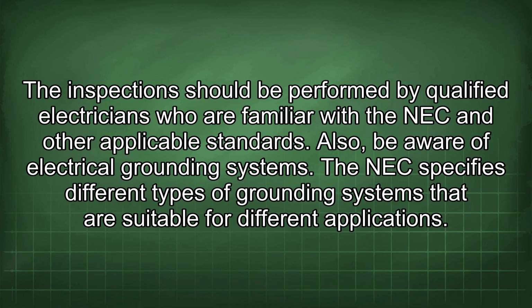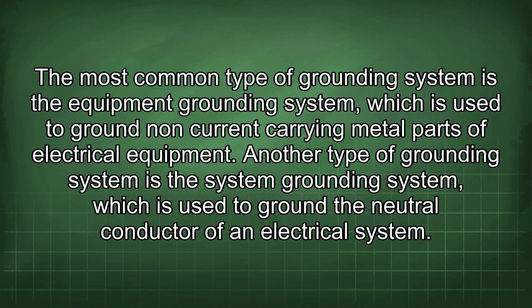The NEC specifies different types of grounding systems that are suitable for different applications. The most common type of grounding system is the equipment grounding system, which is used to ground non-current carrying metal parts of electrical equipment. Another type of grounding system is the system grounding system, which is used to ground the neutral conductor of an electrical system.